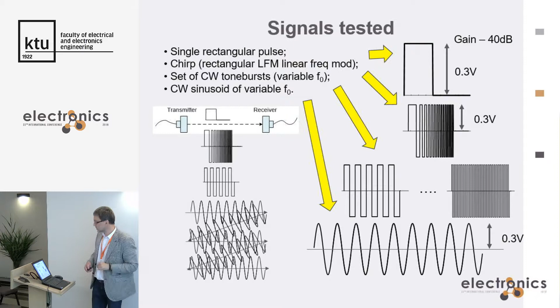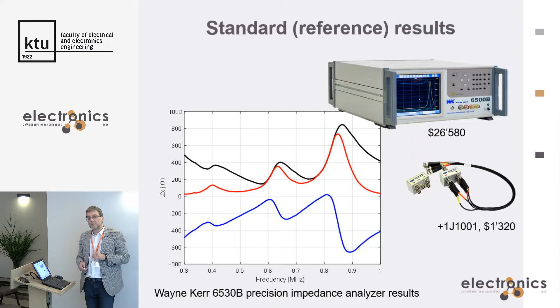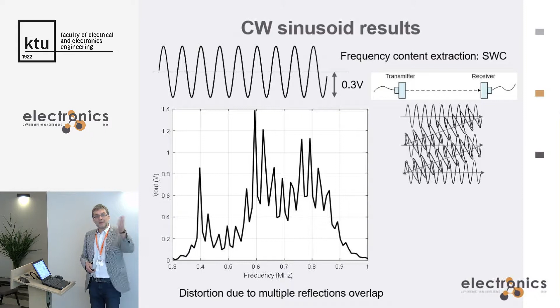Since we wanted some reference measurement, we took an impedance analyzer. I deliberately put the price for this impedance analyzer because it is a really expensive piece of equipment, and besides, it has this continuous sinusoid. But because this time we measured input impedance, and there was no receiving transducer, there was no multiple bouncing. So more or less we were able to measure the impedance with this device. But what is not convenient is that the device is expensive. And these are the results with the continuous wave sinusoid.